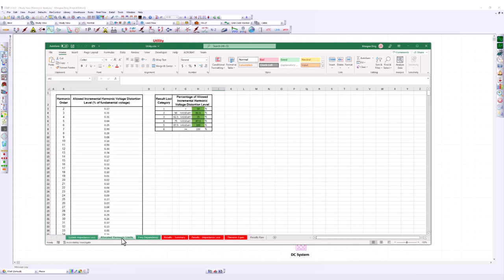And next, let's go to the allocated harmonic limits tab. This tab has the table we saw from the slides, which has all the allowed incremental harmonic voltage distortion levels per harmonic order. We need to fill in all the numbers. Next to it, you will see the percentage of allowed incremental harmonic voltage distortion level with a few threshold values. This is used for color coding of the result figures. In many cases, you can keep the numbers as default. With these two types of data filled in, you can go ahead, save the Excel file, and close it.